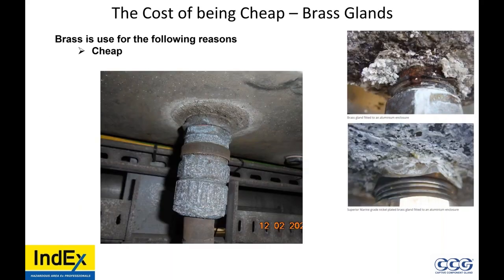Now, cost of being cheap. Brass glands. Why are brass glands used? The only reason is because it's cheap. Or misunderstanding within the industry. So what are the problems with brass? Well, you can't do an inspection on this now. You can't read the EX information. It's going to break off like in the other picture you saw. Dissimilar metals causes corrosion and then it welds to the device, so you can't get it off.